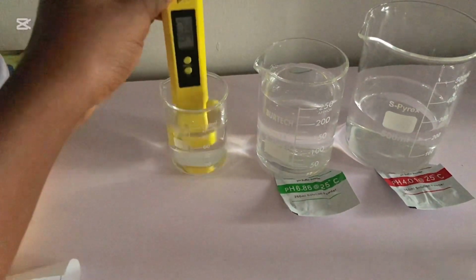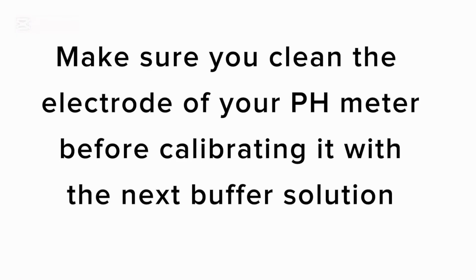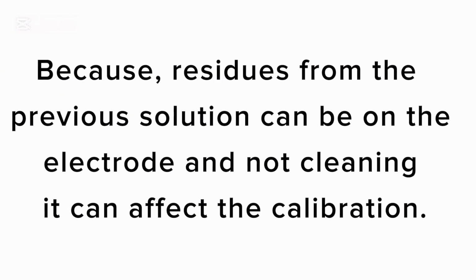Make sure that you clean the electrode of your pH meter before calibrating it with the next buffer solution, because residues from the previous solution can be on the electrode, and not cleaning it can affect the calibration.